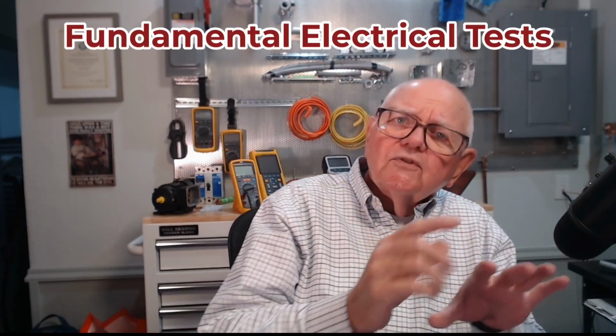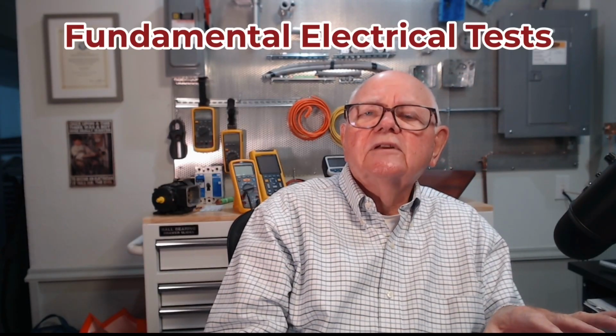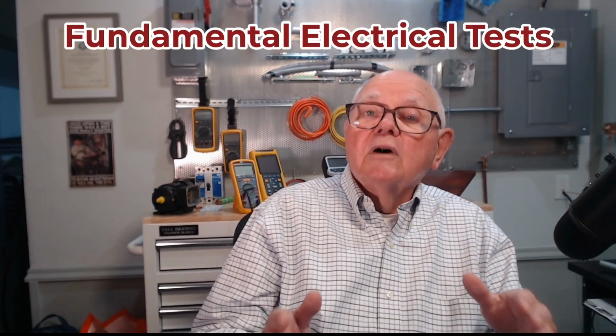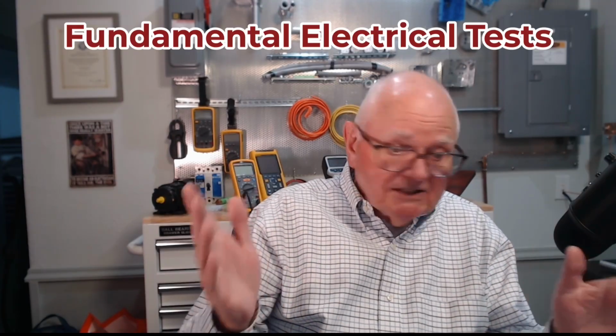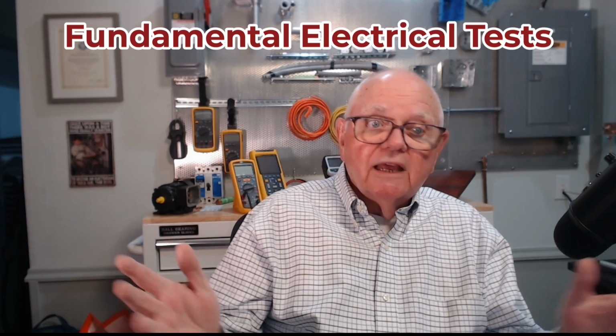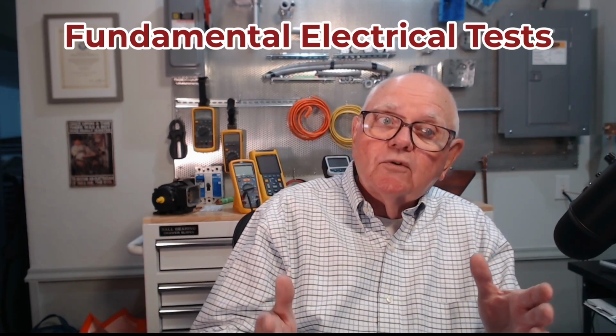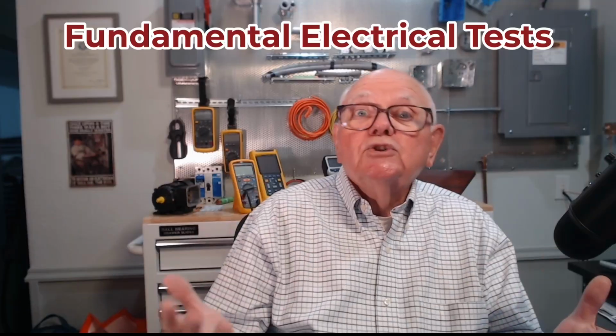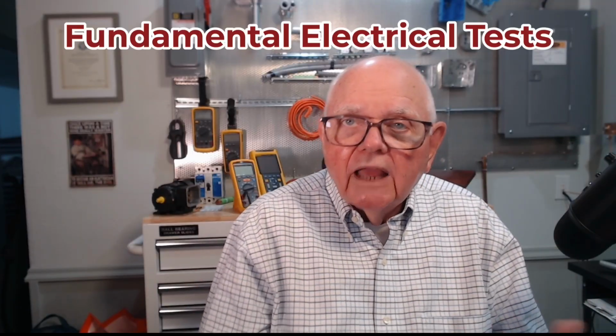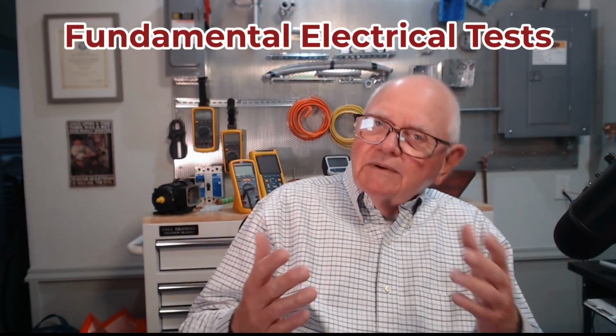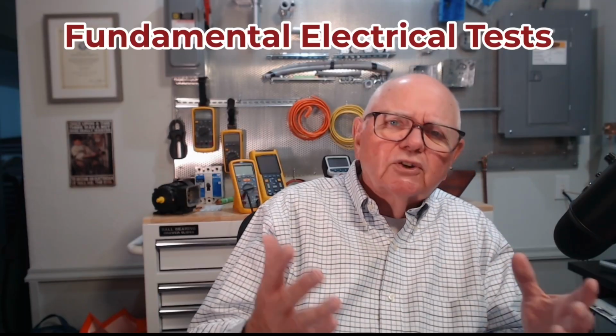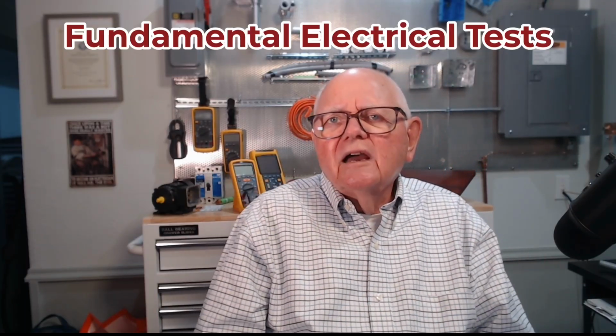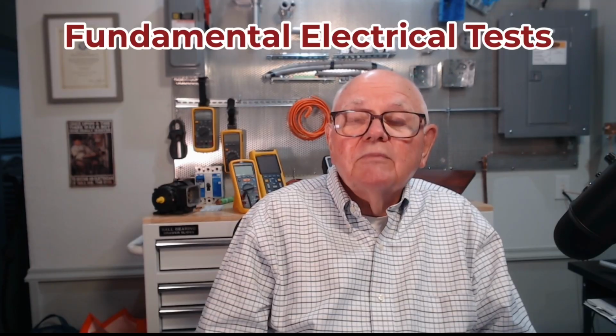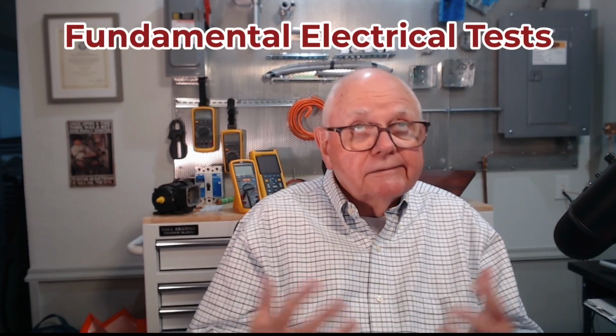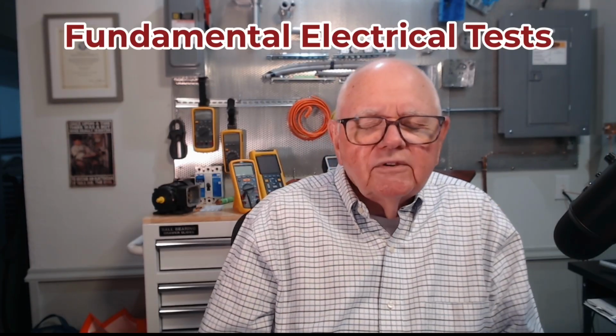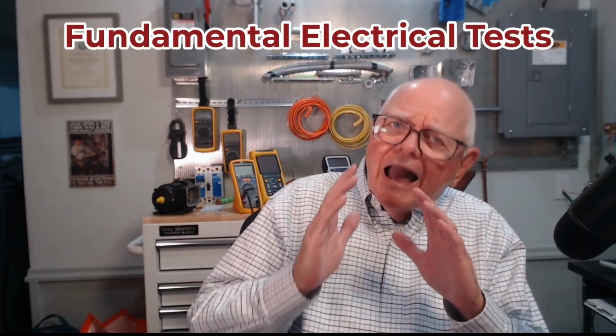Now, if I go through and look at the NFPA 70B standard, it says on certain equipment, I must perform fundamental basic electrical testing. Things like, if I have insulation on a piece of equipment, like an electric motor, let's do an insulation resistance test on it. If I have terminal connections, let's make sure those terminal connections are tight, secure, properly tightened, and that they aren't presenting any high resistance in my circuit, which is, of course, going to cause heat and potential fire and safety issues, obviously. So how do they decide that?